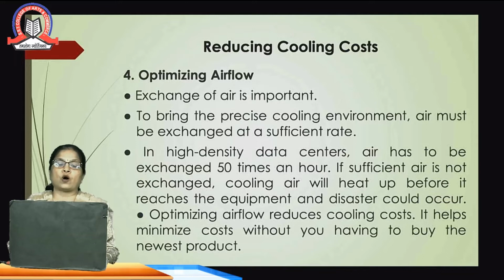Fourth point is optimizing airflow. Exchange of air is important. To bring the precise cooling environment, air must be exchanged at a sufficient rate. In high density data centers, air has to be exchanged 50 times an hour. If sufficient air is not exchanged, cooling air will heat up before it reaches the equipment and disaster could occur.